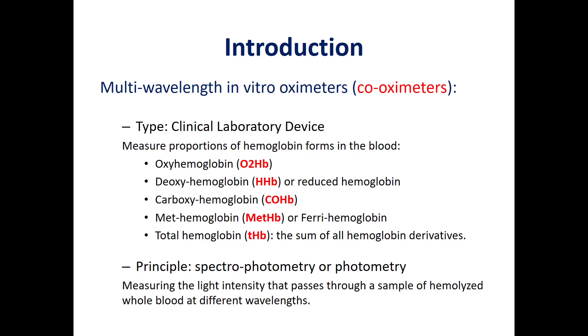The laboratory co-oximeter is a clinical laboratory device. It measures the different forms of hemoglobin, or the different derivatives of hemoglobin. We have oxy-hemoglobin and deoxy-hemoglobin, carboxy-hemoglobin, and met-hemoglobin — the four types of hemoglobin derivatives in our red blood cells.